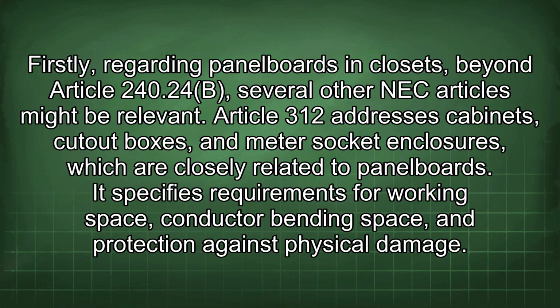Firstly, regarding panelboards in closets, beyond Article 240.24(b), several other NEC articles might be relevant. Article 312 addresses cabinets, cutout boxes, and meter socket enclosures, which are closely related to panelboards. It specifies requirements for working space, conductor bending space, and protection against physical damage.